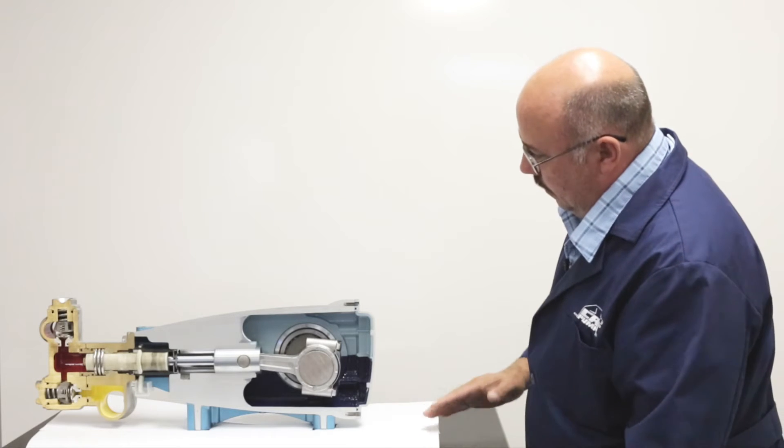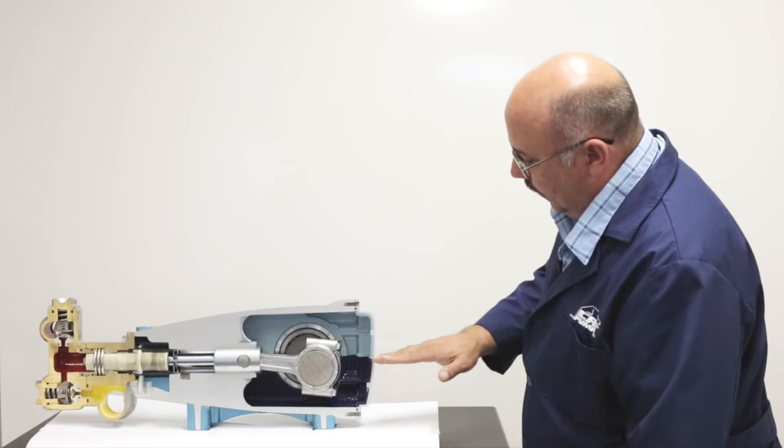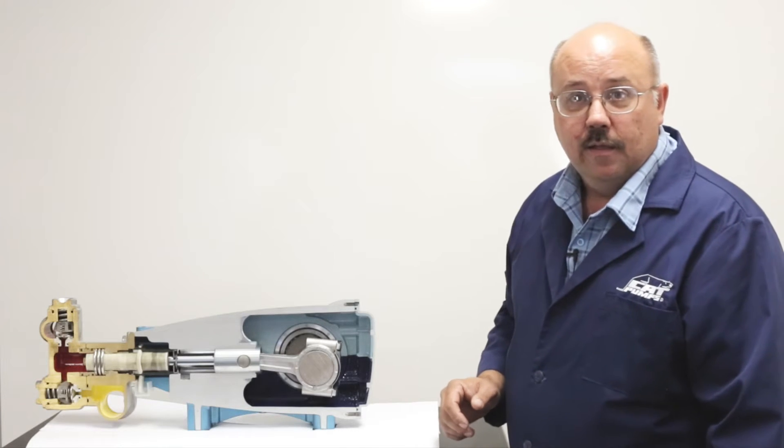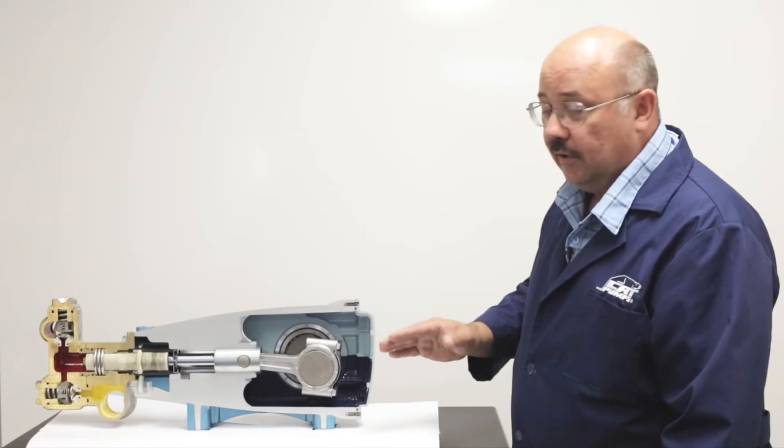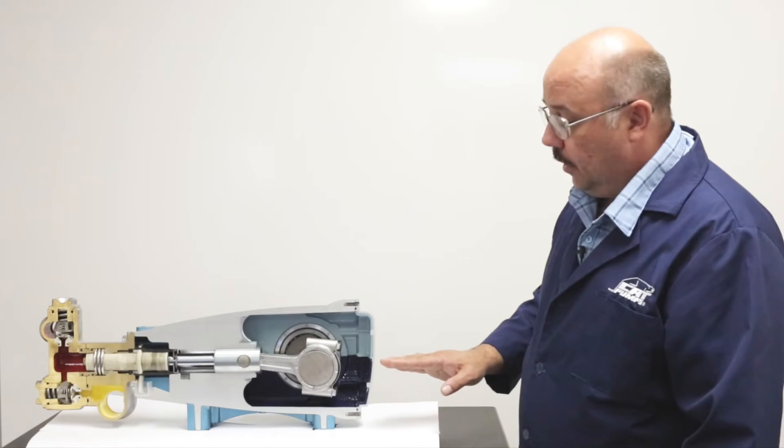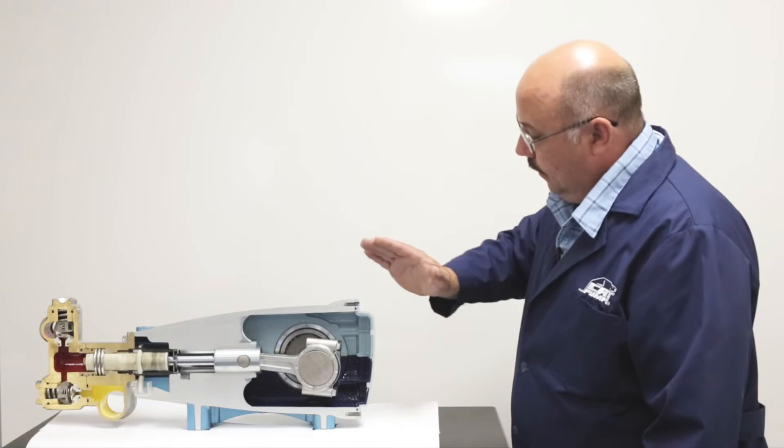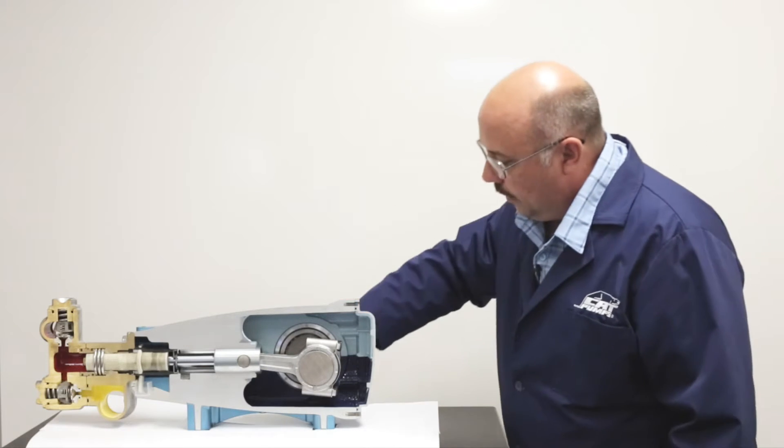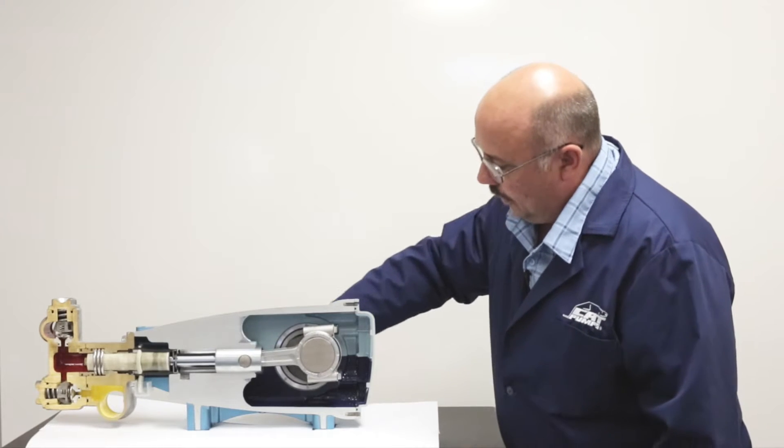Once we get our pump ready to run and we fill it up to here with Cat Pumps oil, which is specially formulated to work with our materials of construction and the loading to give optimal lubrication for all the parts, it's filled up halfway on a bubble gauge or the dipstick, and then we start running our pump and we'll have a motor or something that turns the crankshaft.